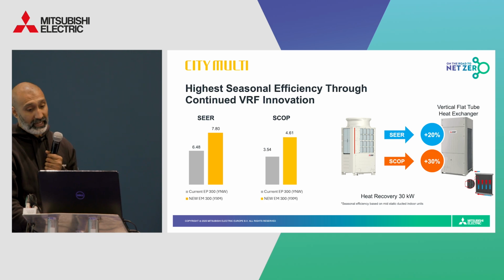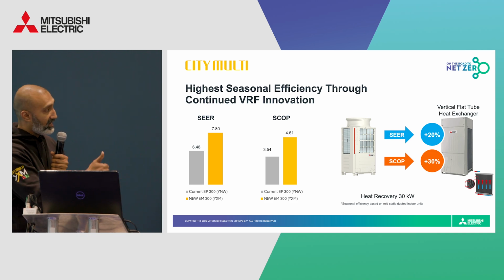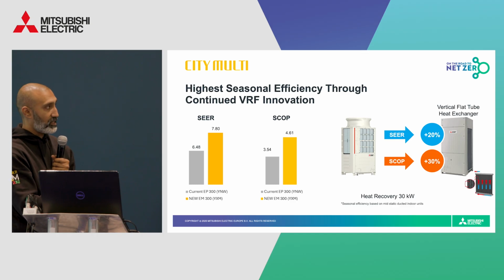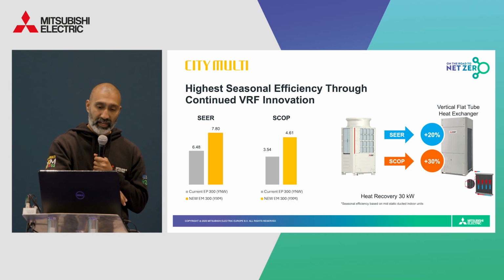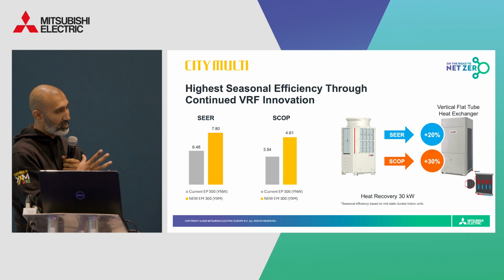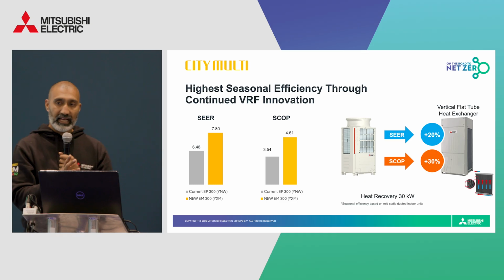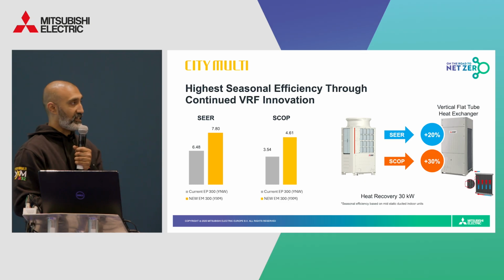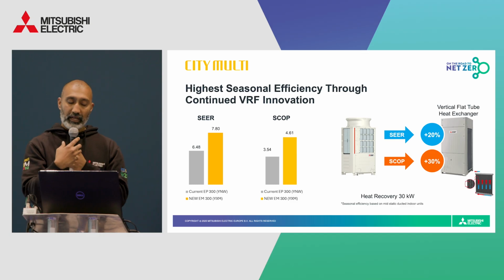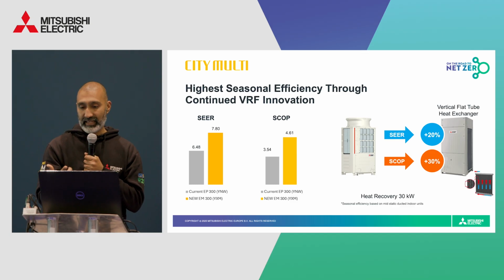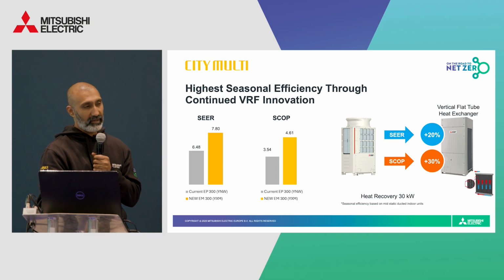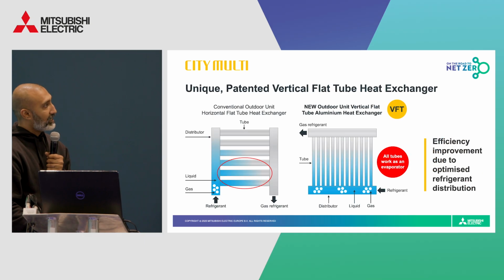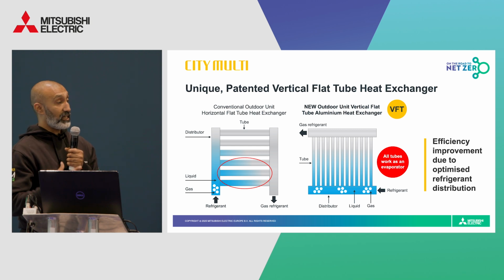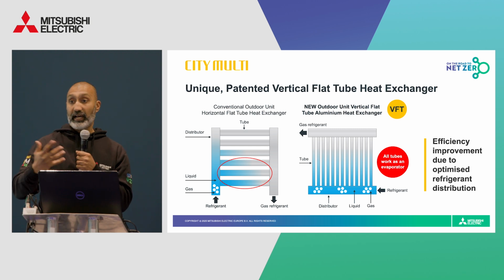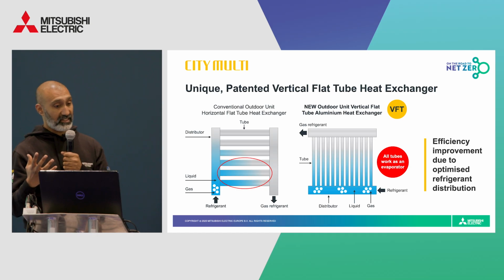So right off the bat, we have improved the efficiency. And here we have a comparison of the SEER and SCOP of the 30 kilowatt YXM R32 solution versus our existing range. And as you can see here, there's been an approximate 20-ish% improvement in the cooling efficiency and a 30-ish% improvement in the heating efficiency. Again, making a really strong case for using the R32 YXM solution in new projects and upgrading, especially where that performance and sustainability is key. Sure. Now, in 2016, when we actually launched the existing chassis, at that time we highlighted our unique aluminium flat tube heat exchanger, which was a big deal, and it really bumped up the seasonal efficiency.